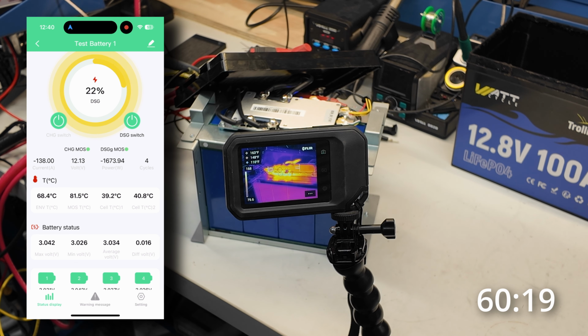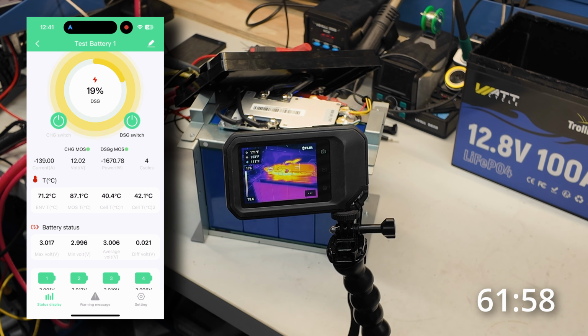We're up to 81.5, or 178.7 degrees. Now up to 82, so probably pushing right at 180 degrees. All right, we are at 87 degrees Celsius, 188.6 Fahrenheit, 18% state of charge, drawing 139 amps. We're going to run out of battery here pretty quickly, so I'm going to get obnoxious and increase our loads rather significantly.